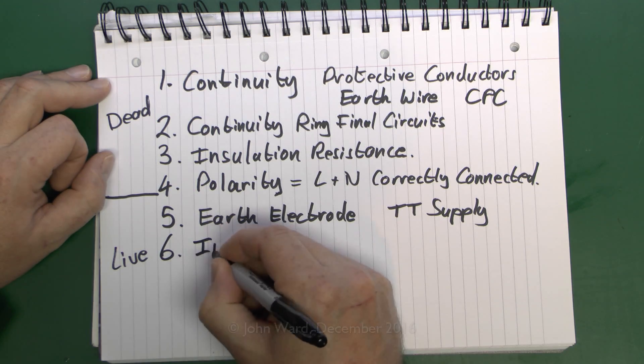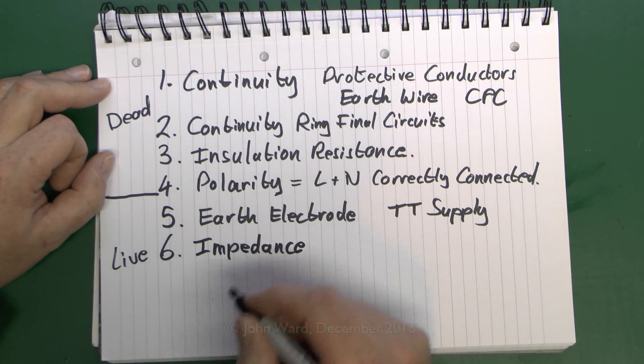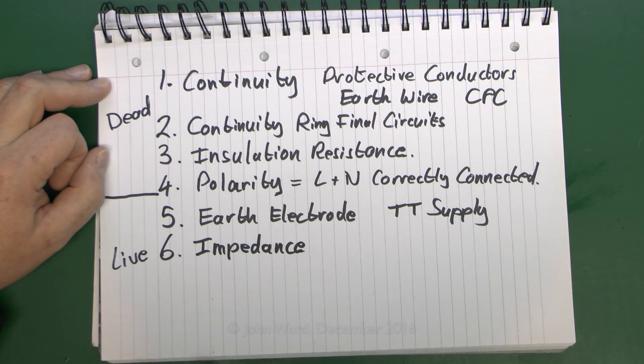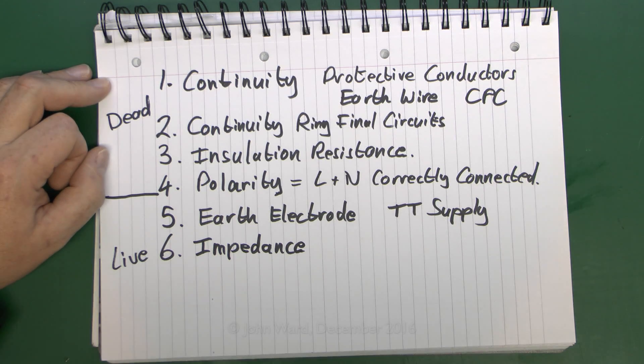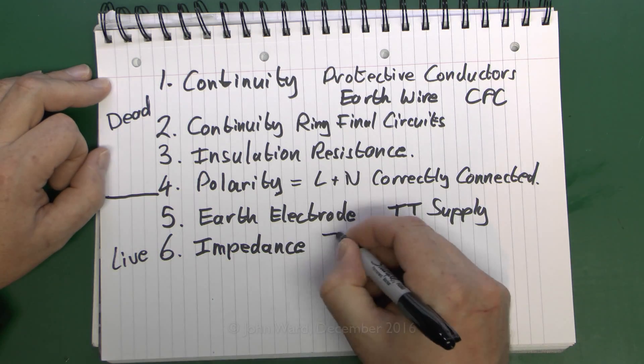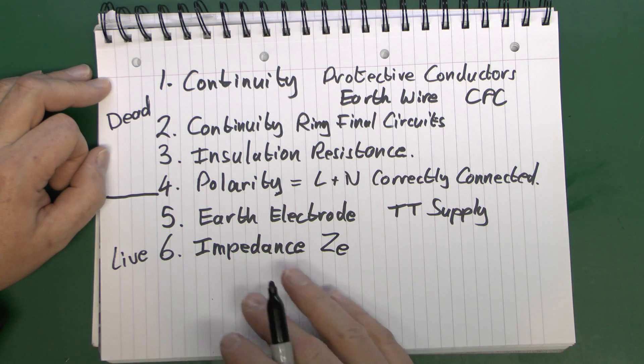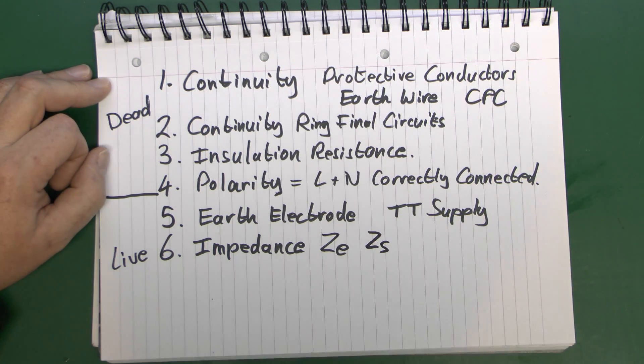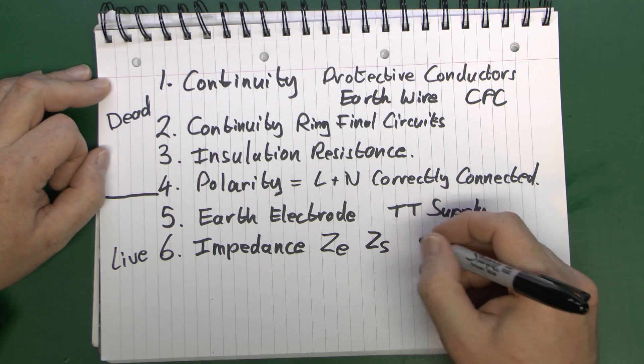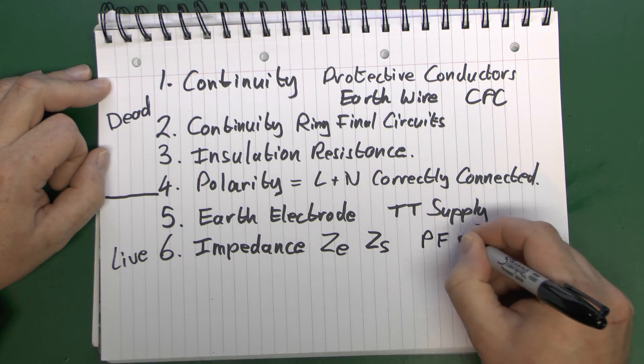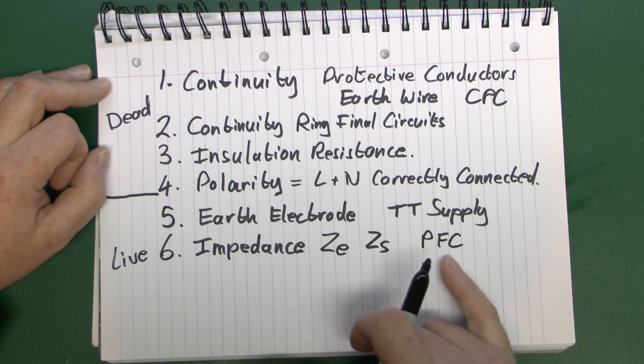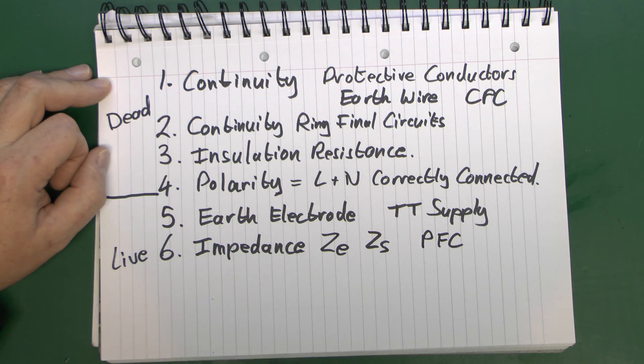Moving on, we have impedance — or more correctly, the earth loop impedance. This involves confirming that the supply, or the electrode, has the correct impedance. For the external impedance, generally referred to as ZE, you also need to check the impedance of individual circuits to make sure that the devices will trip within the required time — that's generally given the symbol ZS. At the same time, you can actually check the prospective fault current: the current that would flow if the supply were shorted out. That's important in some installations depending on what protective devices you have installed.